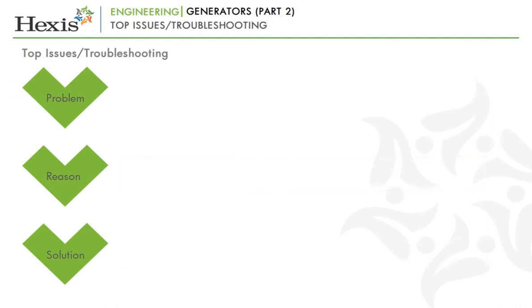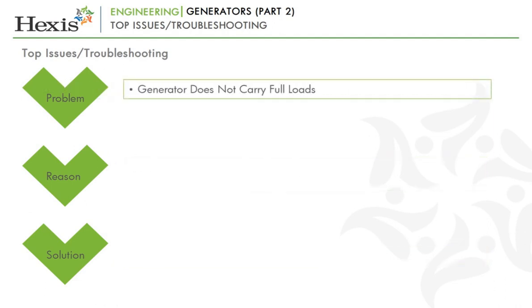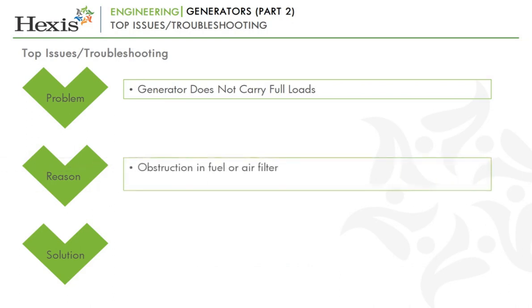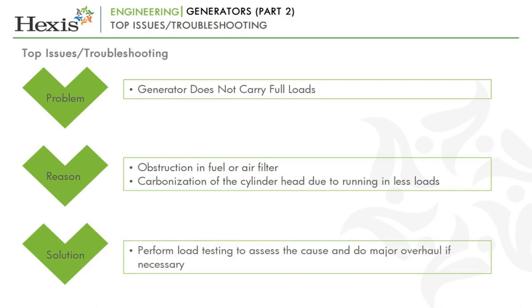Problem: generator does not carry full loads. Reason: obstruction in fuel or air filter. The other reason could be carbonization of the cylinder head occurs if engines are regularly run in underload conditions. Solution: load testing may be required to assess the cause and a major overhaul may be necessary.